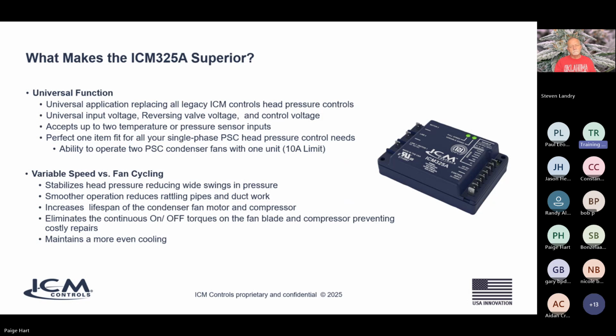So what makes the ICM325A superior to other types of head pressure control on the market? Well, one of the big things is the universal function of our control versus some of the other controls that are out there. Ours can replace literally all of the legacy ICM head pressure controls we had before. So this is a one-part-fits-all to all our past head pressure controls, which had different SKUs for different voltages and different reversing valve operation. Now all of that is combined into one universal control, which makes it really nice for our distributors and our customers. You've got a one-stop shop for your head pressure control.